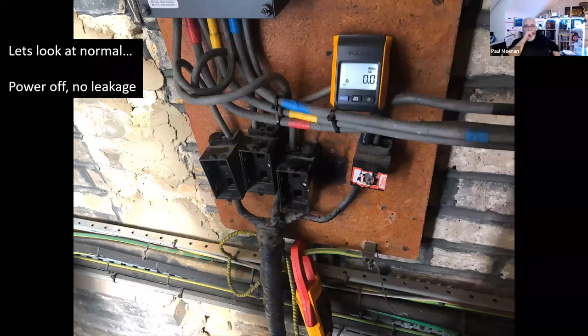So what we've got here is a three-phase supply. All the fuses are taken out, and we've got a clamp meter on the main earth conductor, with a separate display so you can see it. Unsurprisingly, we've got no current there whatsoever, so zero. That's exactly what you'd expect - no power going through the installation, and no current there either. So that's what normal looks like.